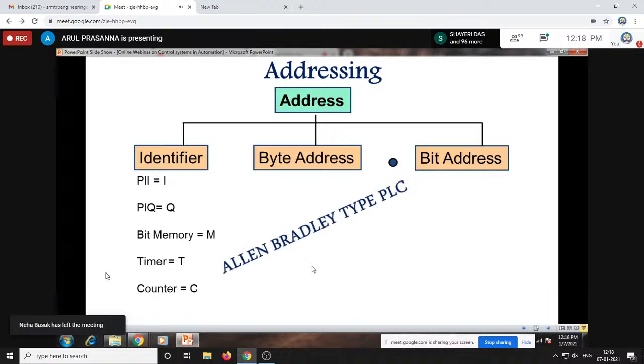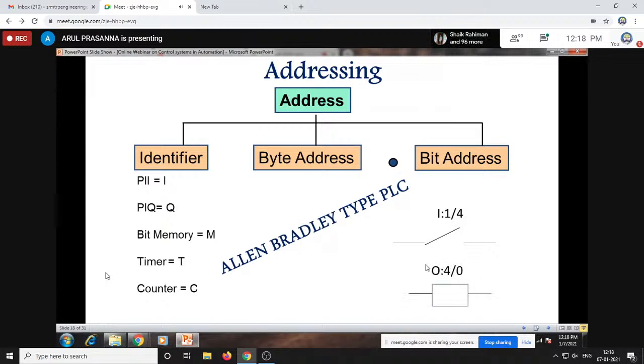Then how about competitors like Allen-Bradley? They use the identifier I for input, and instead of I1.4, they use a colon with 1/4. This is the methodology for addressing an input on an Allen-Bradley type PLC. Similarly for output, instead of Q they use O, then a colon and 4/0, so 4.0 is addressed as 4/0. It is a little bit changed, but the logic remains the same for all types of PLC.